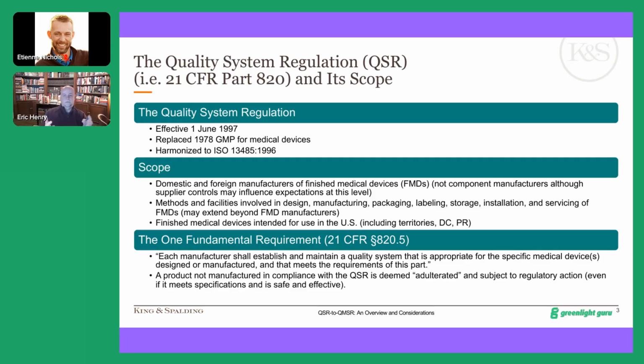And obviously, the U.S. can't set regulatory policy for areas of the world outside of its borders, but within the U.S., the contiguous 48 states and the 2 states of Alaska and Hawaii, as well as the District of Columbia, the U.S. territories, and Puerto Rico are all within scope of the quality system regulation. There's one big requirement here, and that is that you have a quality system and that it's appropriate, and that it meets the requirements of this part, meaning 21 CFR Part 820. We're going to hit this last bullet again later on in the presentation.